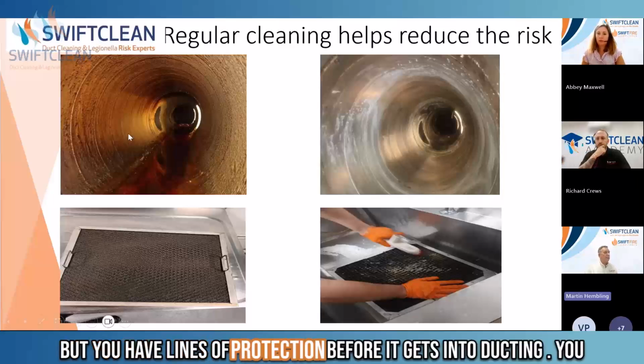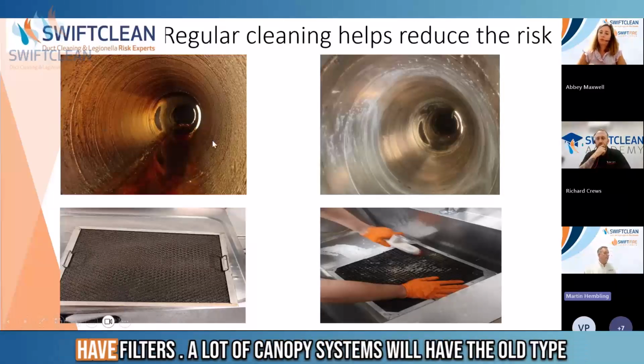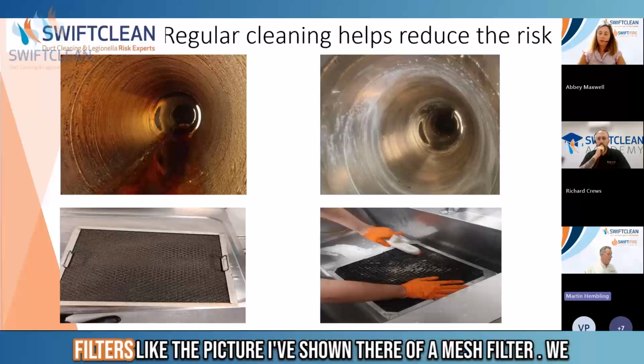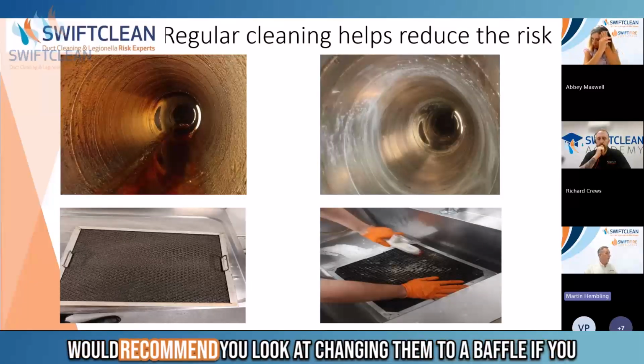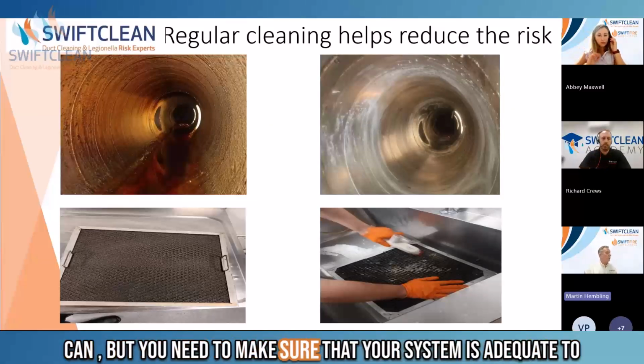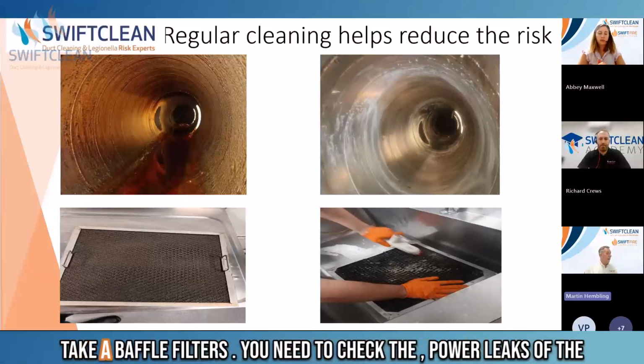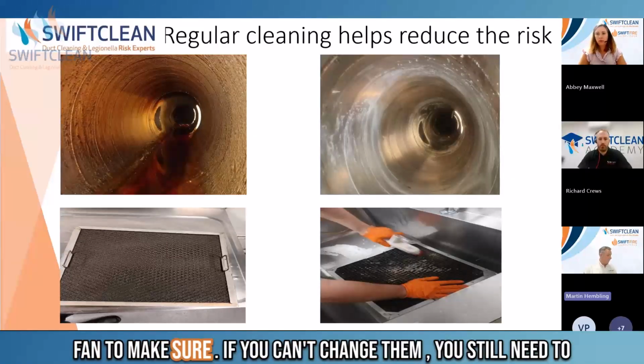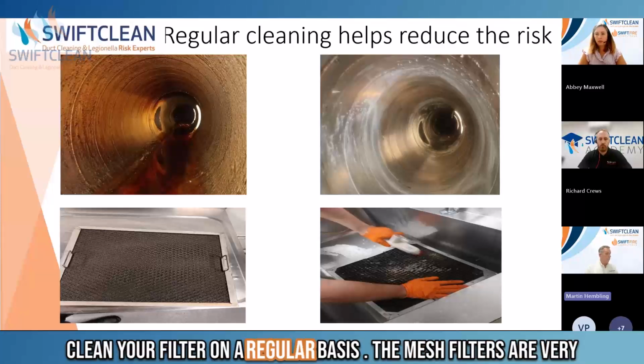But you have lines of protection before it gets into the ducting - you have filters. A lot of canopy systems will have the old type filters, like the mesh filter shown here. We'd recommend looking at changing them to a baffle if you can, but you need to make sure your system is adequate to take a baffle filter - check the power of the fan to make sure. If you can't change them, you still need to clean your filter on a regular basis.